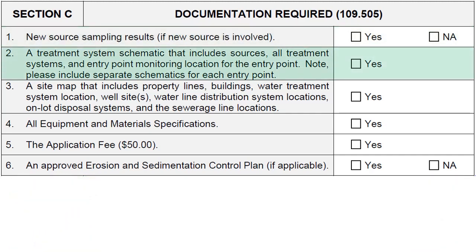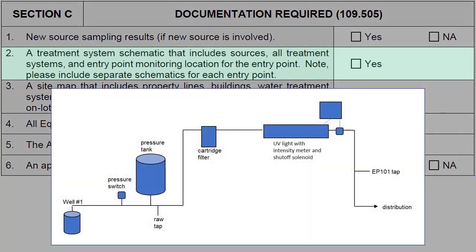A treatment system schematic must also be included. This may be computer generated or hand drawn, and should include all sources, treatment systems, dimensions of raw and finished water storage vessels, and the entry point monitoring location. Include separate schematics for each entry point. Here is an example of a simple schematic for a non-community system. Note that the well, the treatment, and the entry point 101 TAP are all indicated on this schematic.